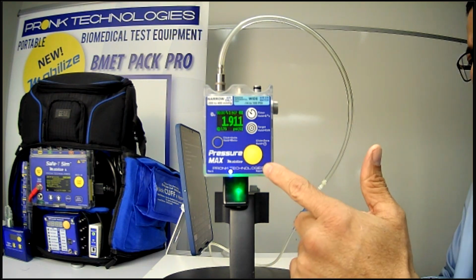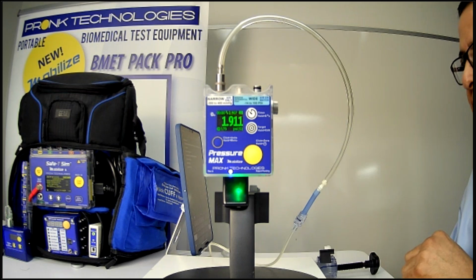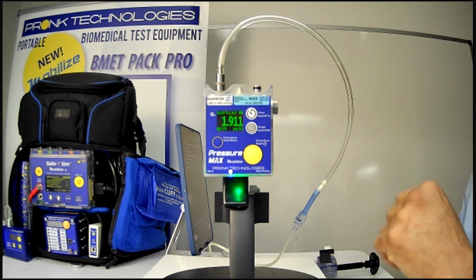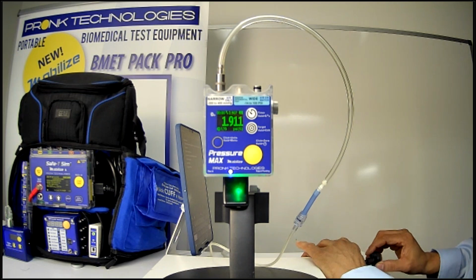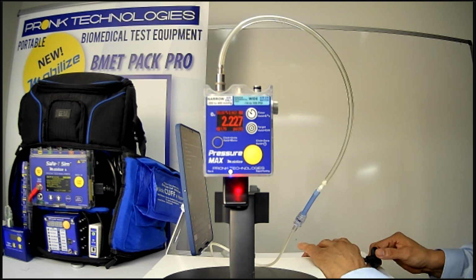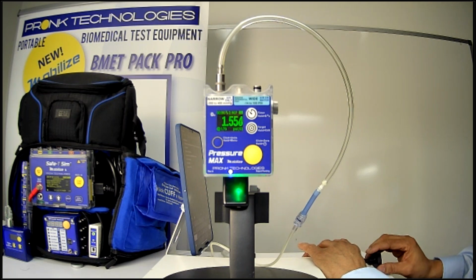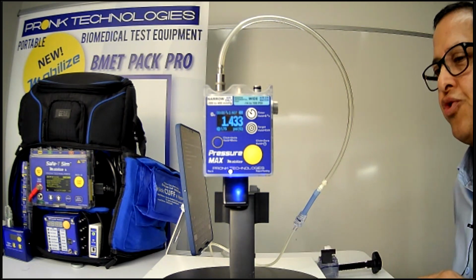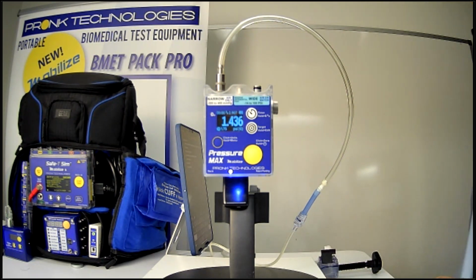You also hear a beeping sound. That's an audible tone. You can enable or disable it. It's just an audible confirmation that your result is within tolerance. Again, if I go over it with the tone on, you'll hear a different tone letting you know you're over the target. And when you're below the target, there is no audible tone at all. So it's a nice indicator for you to know whether your pressures are within the target or not.